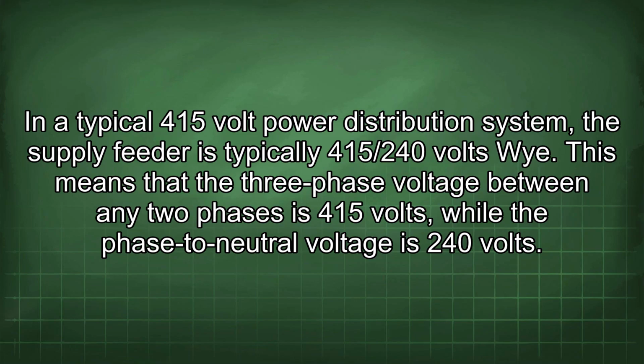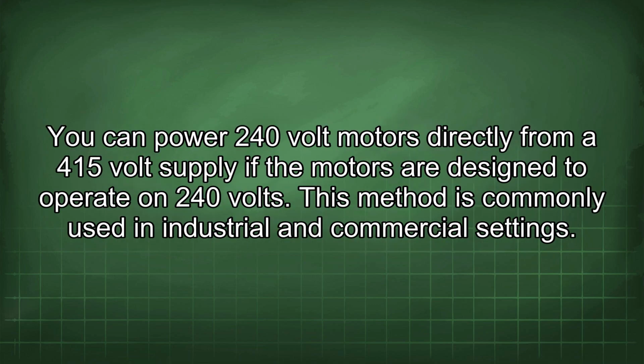In a typical 415-volt power distribution system, the supply feeder is typically 415/240 volts Y. This means that the three-phase voltage between any two phases is 415 volts, while the phase-to-neutral voltage is 240 volts. You can power 240-volt motors directly from a 415-volt supply if the motors are designed to operate on 240 volts. This method is commonly used in industrial and commercial settings.